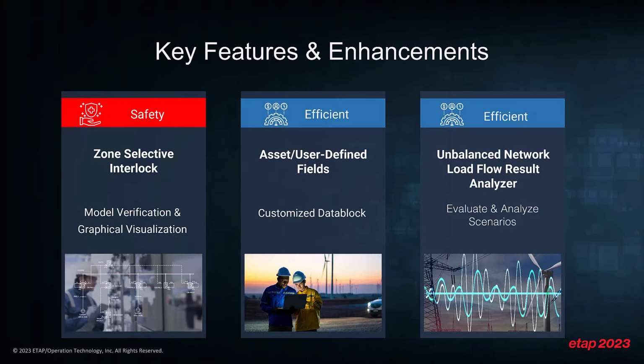Zone Selective Interlocking, or ZSI, is a communication scheme used with electronic trip units for circuit breakers to improve the level of protection in a power distribution system. This is of course achieved through communication with the downstream and upstream devices in the network. Previous releases of ETAP already included the ability to model and connect ZSI wiring to simulate the impact of the logic in terms of protection and arc flash studies. ETAP 2023 now expands on that capability by visualizing the ZSI wiring on the single line diagram and ensuring that there are no gaps in the information needed by engineering and maintenance to safely commission and maintain these devices and the logic.